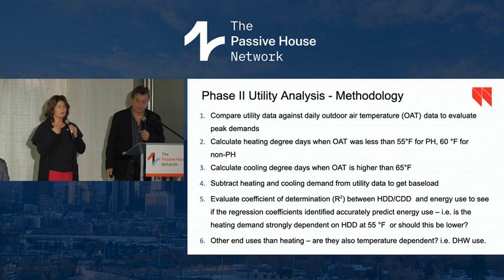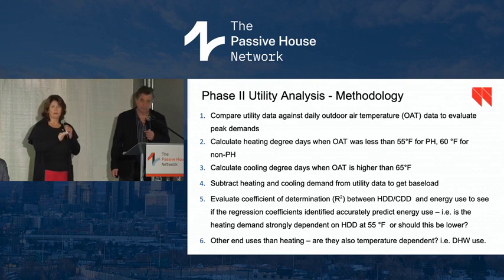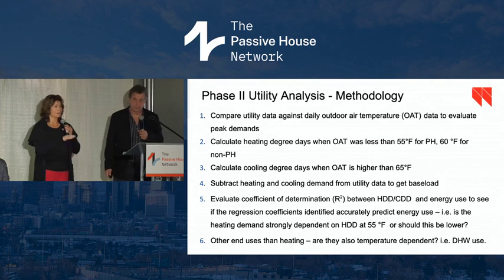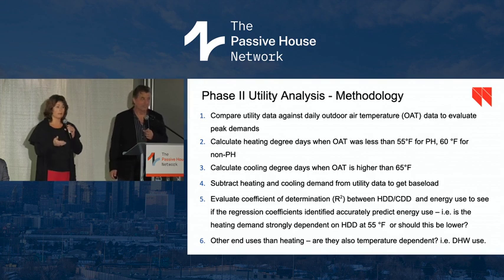The building owner said they don't really need heat. When they get complaints about when the heating can be turned on, it's usually around when the temperature doesn't go higher than 55 degrees during the day, so then they turn it over from cooling to heating. If they get complaints from occupants, only about once or twice a season, they just tell them it's an energy efficient building, please put a sweater on, we'll turn the heat on this date, it's really not needed. They've had tenants tell them they've never turned their heat on.